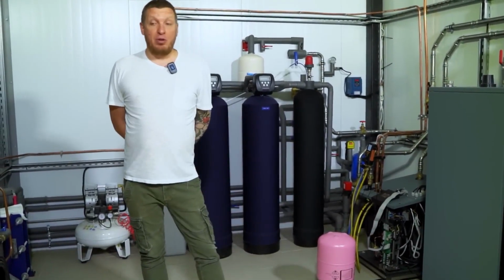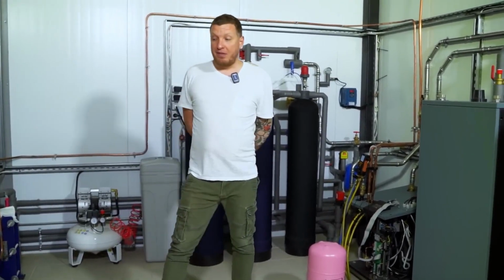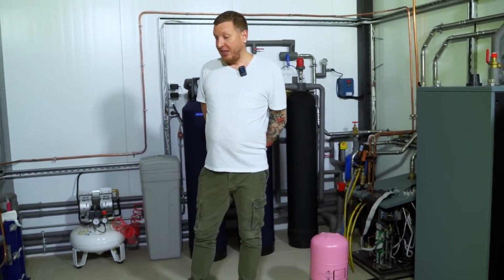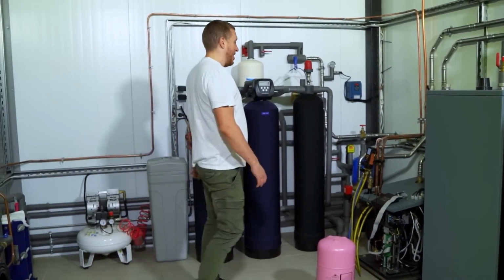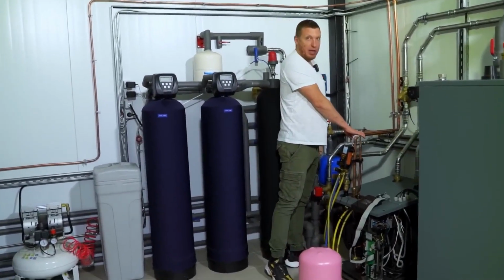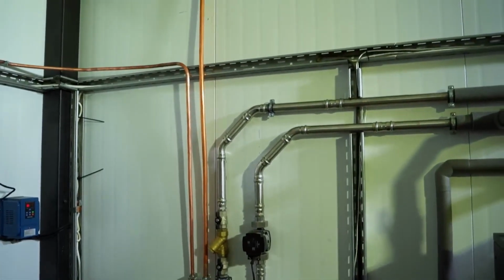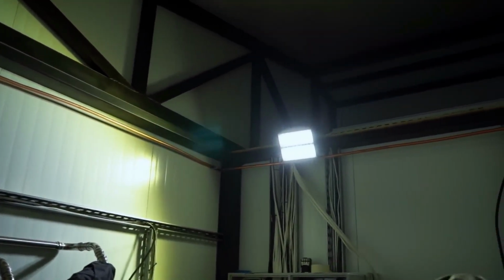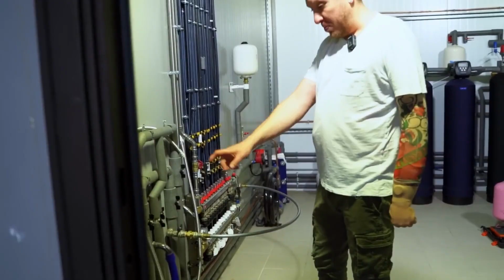So for the hot side, we use direct condensation into the floor. Now I'll explain how this is done. Look, two pipes run from the heat pump to the condenser. Here they are, supply and return. Here they go running along. Later, all of this will be insulated. It goes over here, I'll show you later, and heads to the manifold.